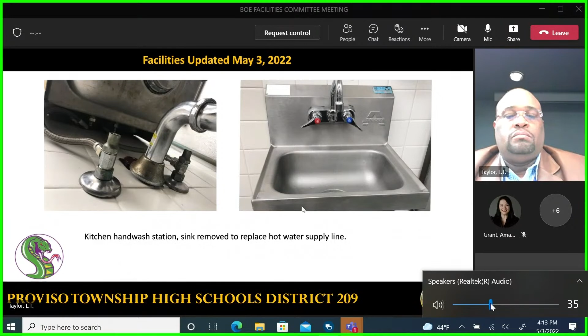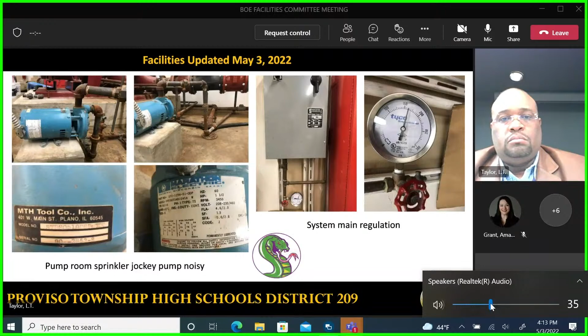In our pump room for the fire suppression system, we have our jockey pump. We had an incident where one of the nipples recently burst from corrosion—I believe those slides will be coming forward. The jockey pump's bearings appear to be a little noisy, so we're monitoring it right now. It runs typically around 160 PSI for the entire system, so we're keeping an eye on that.